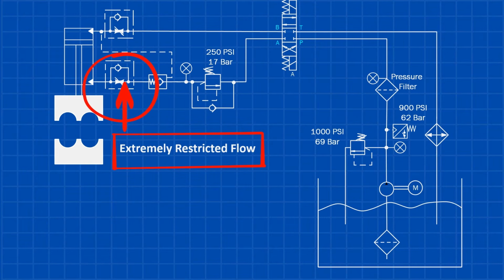design flaw. This usually happens with overhung loads. Here's the situation. If the system has a flow control on the rod end side, which is typically metered out, and it's turned down too much to slow the extend stroke, it can interfere with the counterbalance valve operation. Since the rod end piston area is smaller than the blind end, a sudden valve shift can cause a pressure spike on the rod end. Over time, this pressure spike can lead to packing gland failure.